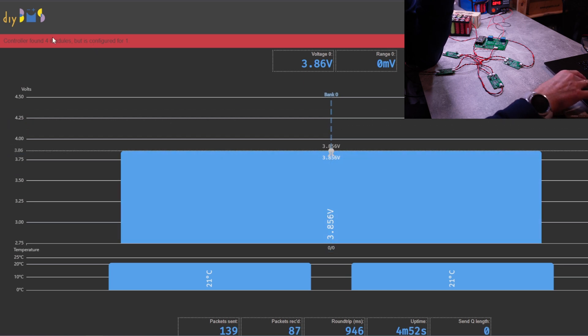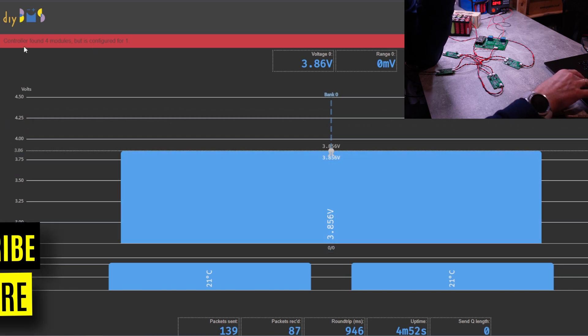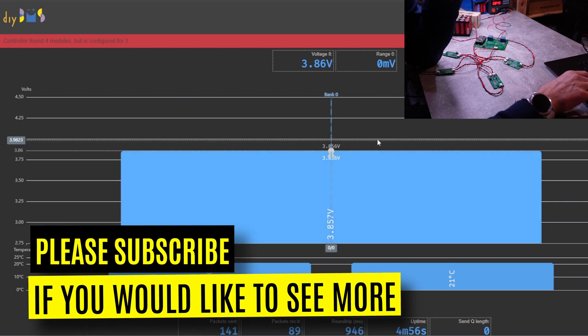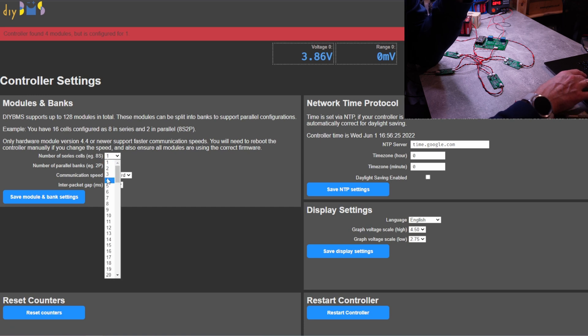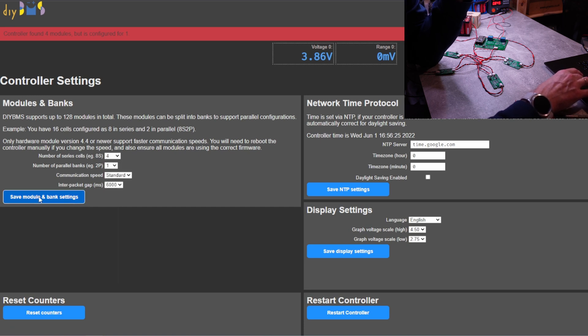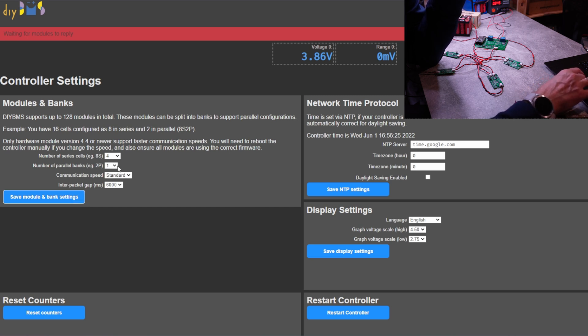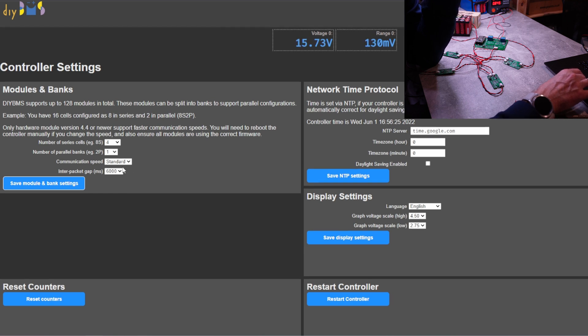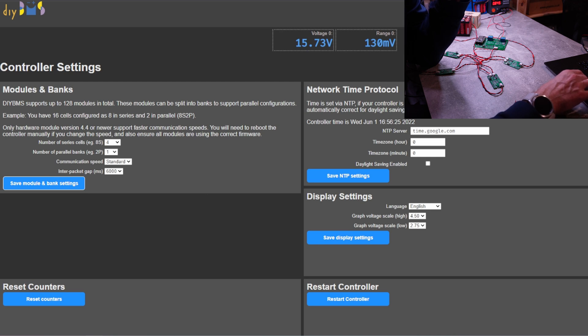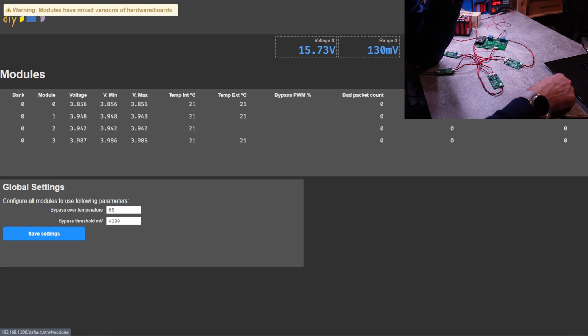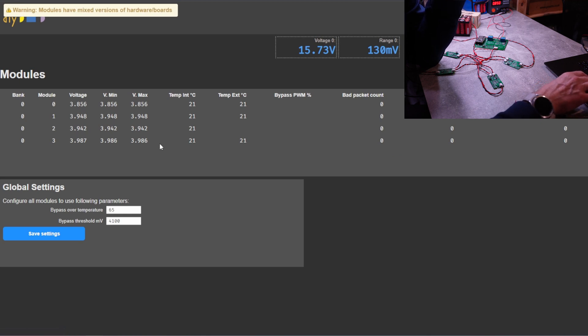And we have an error that controller found four modules but we configured for only one module. Okay, so that's where we have four modules. But we have a number of parallel banks. So in this case we have only one bank. And hopefully now we should get our four modules.